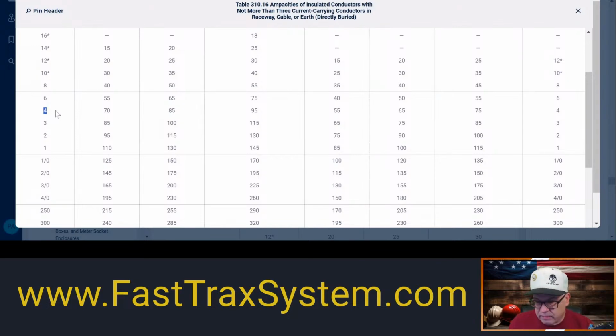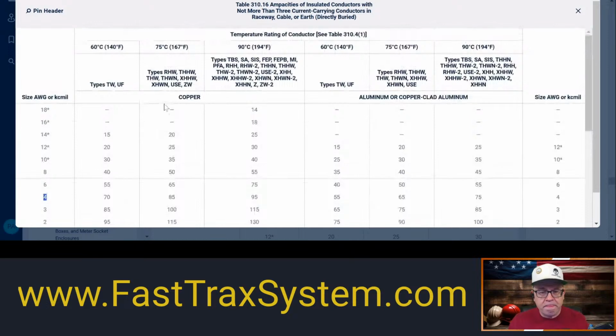Okay, right? Now, some people will say, Paul, it's under 100 amps. It didn't really say conductor size. Why didn't you use the 70 under the 60 degree? Well, the reason for that is that typically your continuous duty motors, and it explains this, by the way, in the lesson when you're in the program. It explains why it uses the 75. But if you go look at 110.14(C), you'll see that it talks about motors. In motors, you use the 75. Okay, so that is why we automatically just go to the 75.